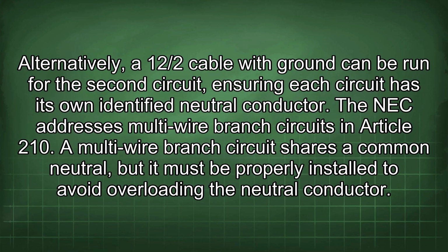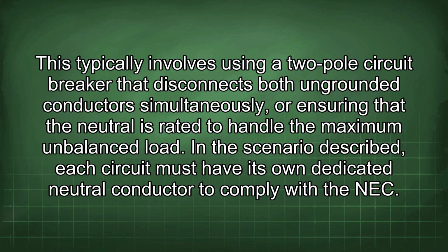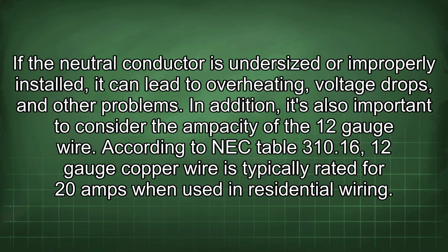A multi-wire branch circuit shares a common neutral, but it must be properly installed to avoid overloading the neutral conductor. This typically involves using a 2-pole circuit breaker that disconnects both ungrounded conductors simultaneously, or ensuring that the neutral is rated to handle the maximum unbalanced load. In the scenario described, each circuit must have its own dedicated neutral conductor to comply with the NEC. If the neutral conductor is undersized or improperly installed, it can lead to overheating, voltage drops, and other problems.